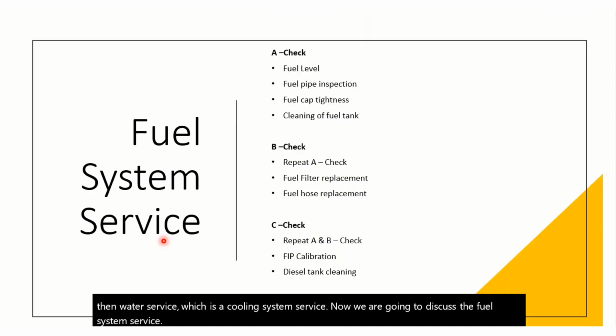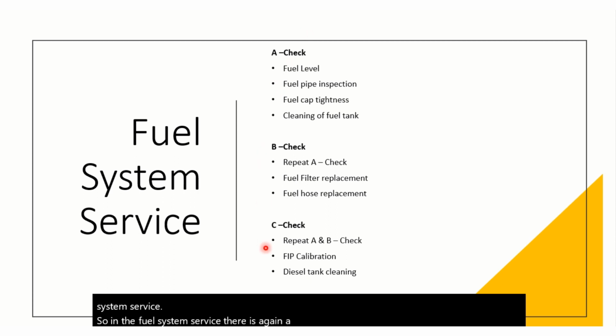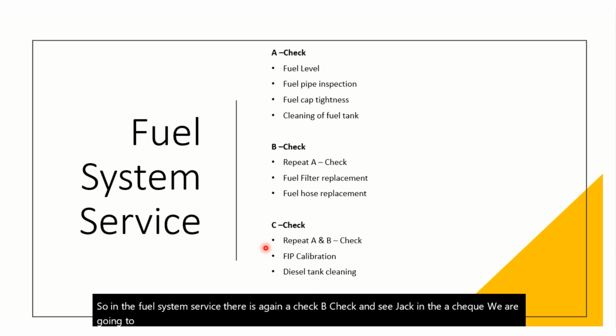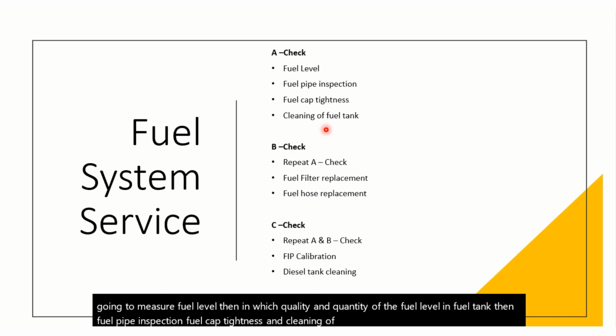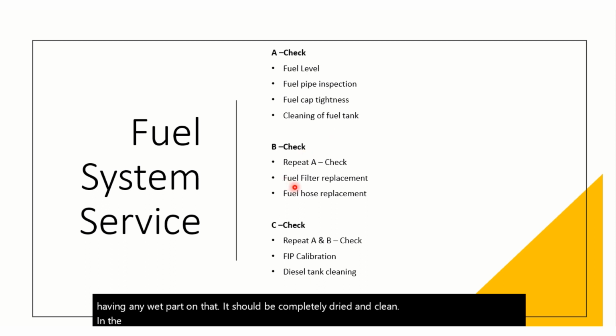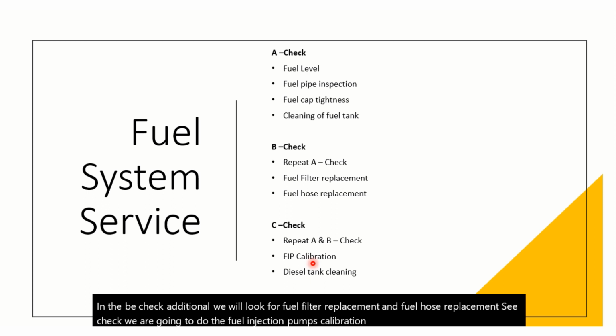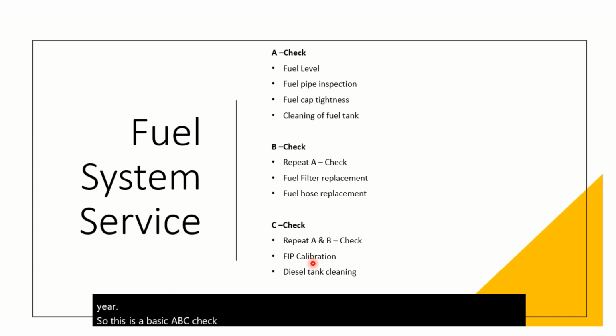In the fuel system service, there is again A check, B check and C check. In the A check, we are going to measure the fuel level, the quality and quantity of the fuel in the fuel tank, then fuel pipe inspection, fuel cap tightness and cleaning of the fuel tank. The fuel tank should not have any wet part on it, it should be completely dry and clean. In the B check, additionally we will look at fuel filter replacement and fuel hose replacement. In the C check, we are going to do the fuel injection pump calibration and diesel tank cleaning every year. So this is the basic ABC check of the fuel system service.